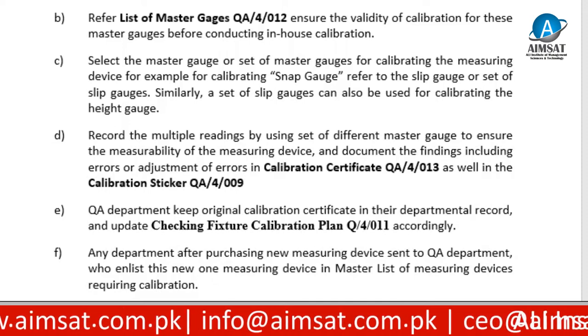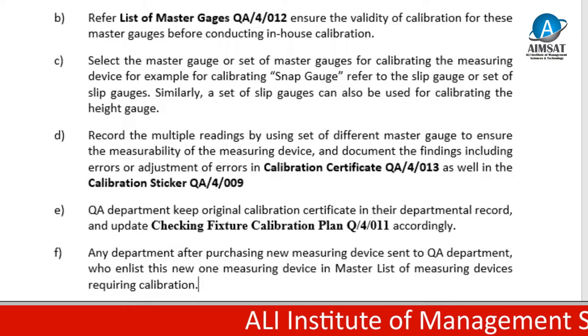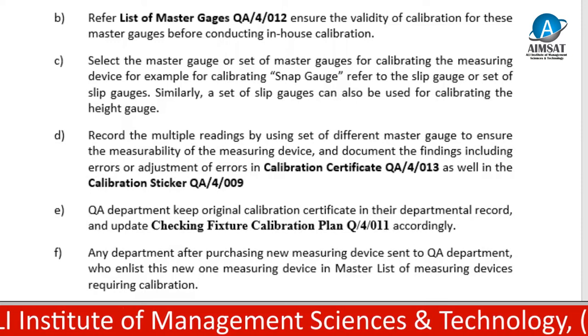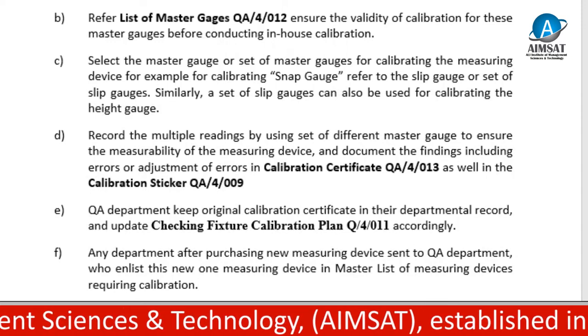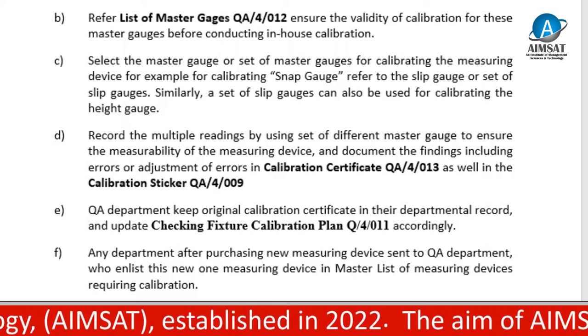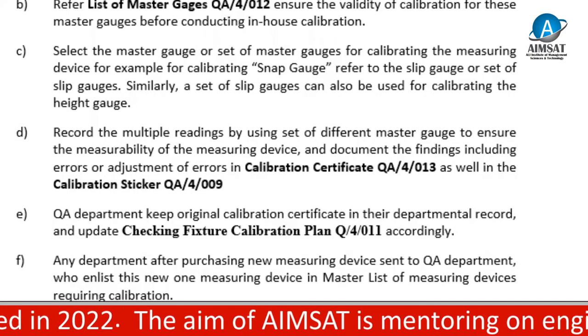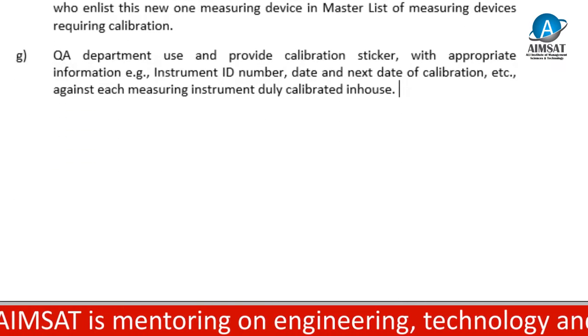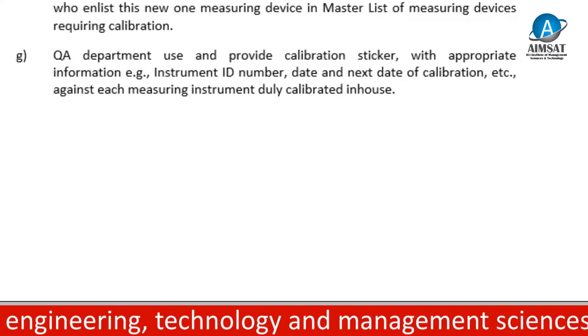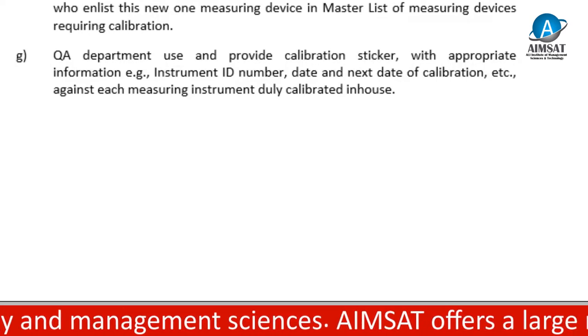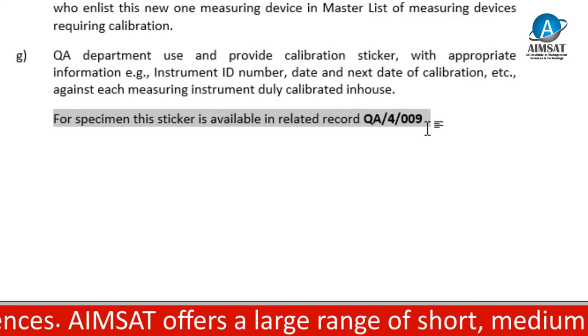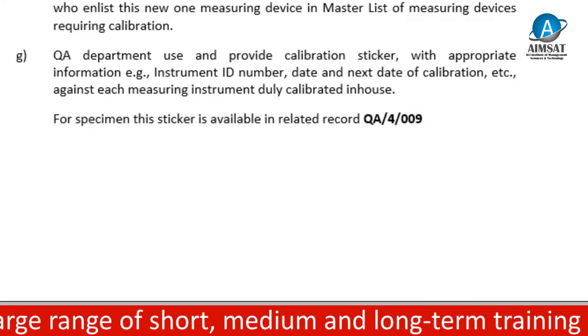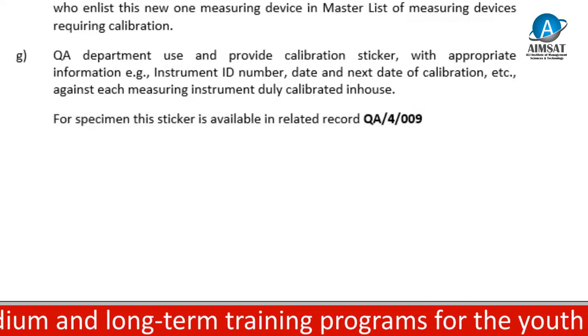Any department, after purchasing a new measuring device, sends it to the QA department, who enlist this new measuring device in the master list of measuring devices requiring calibration. The QA department uses and provides a calibration sticker with appropriate information, for example instrument ID number, date and next date of calibration, against each measuring instrument duly calibrated in-house.